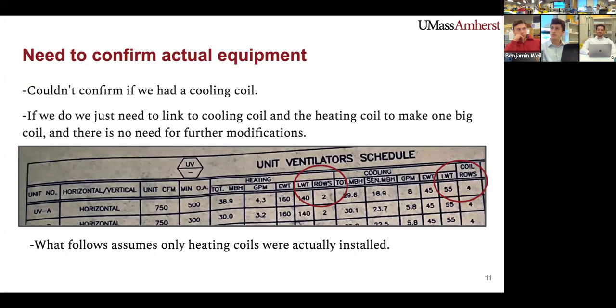During our site visit, we assumed that there was only a hot water loop that contained heating coils, and it didn't occur to us to look for cooling coils until after analyzing this unit ventilator schedule. You couldn't imagine that this was a system that would be designed to have both a cooling and heating coil while only utilizing heating. But if that's something you can confirm by looking at the equipment, then the solution will be as easy as combining the cooling coils and the heating coils to make one giant coil. And that is a simple solution.